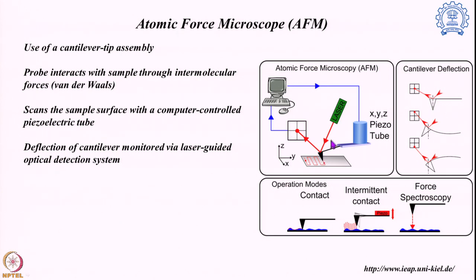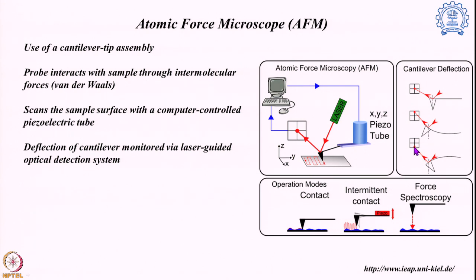The movement of this tip is monitored by the laser optical detection system. The laser hits the top of the tip, gets reflected, and is monitored by the optical detection system. If the cantilever and tip are level, the laser hits a particular position on the optical detector. If the tip moves upward, the reflected laser is detected at a different region showing upward movement; if it goes down, the laser is detected at the bottom region of the optical detection system. With this laser and optical detection technique we can follow even minute changes detected by the tip.